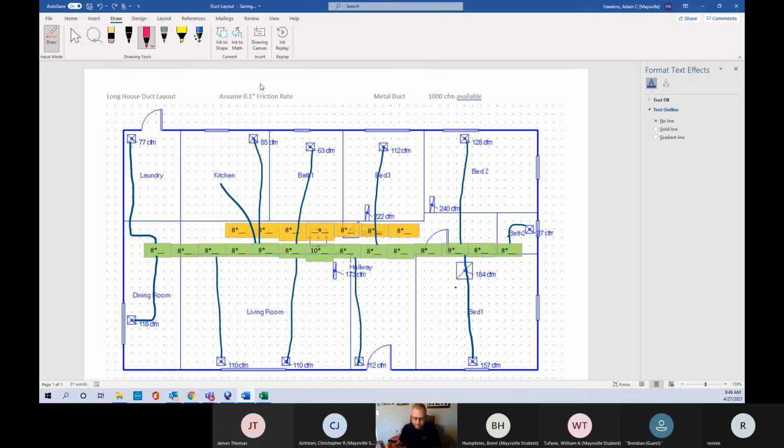All right, so in his example, he said this booth, he'd done a bunch of research on his own. This booth may be 8 feet square. It's not very big at all. If I'm sizing by rough sizing, a 5-inch duct should be plenty, 50 CFM of air or something. Now he's saying, okay, 50 CFM of air, so many BTUs. I've got a dude in there playing a guitar. He's sweating, he's big, whatever. So maybe give him 100 CFM of air.